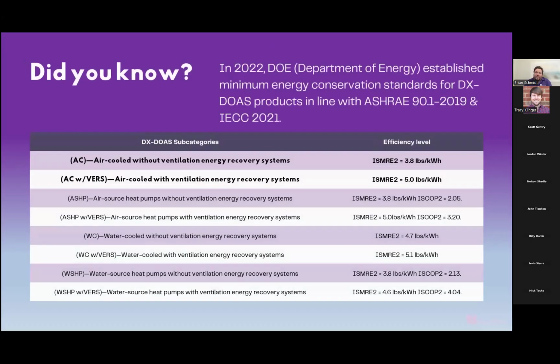The federal minimum for ISMRE2 values for air-cooled without an ERV is 3.8 pounds per kilowatt hour. For air-cooled with an ERV, it is 5 pounds per kilowatt hour. Now, I will preface this by saying the number you're about to see from Mojave is without an ERV. We do have the ability to put an ERV on these systems. If it's required by local code, certainly you can put an ERV on these systems. However, I would dare to say it does not affect the rating very much. So again, federal minimum without an ERV is 3.8, with an ERV is 5.